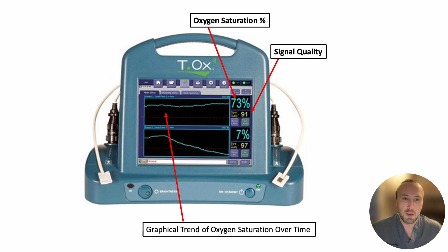There is considerable variation in tissue oxygenation between individuals, flaps, and different areas of the same flap. For percentage oxygenation, the relative trend in oximetry value over time is more important than an absolute value. Remember, the flap percentage oxygen saturation frequently differs from the patient's pulse oximetry value. Parameters and thresholds are set by the surgeon. These should not be changed by the staff.